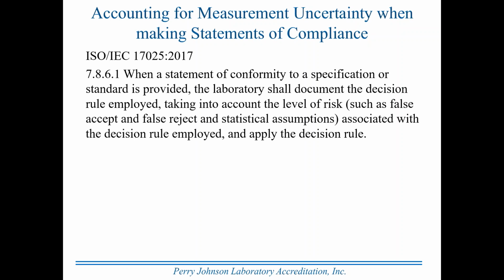Okay, let's talk a little bit about accounting for measurement uncertainty for making statements of compliance. Very important. Again, this is taken verbatim from the standard 7.8.6.1. When a statement of conformity to a specification or standard is provided, the laboratory shall document the decision rule employed, taking into account the level of risk, such as false accept and false reject, and statistical assumptions associated with the decision rule employed, and apply the decision rule. So this is an effort to pin down specifically what the writers of the standard, the authors, wanted to see happen when accounting for measurement uncertainty, making a statement of compliance.